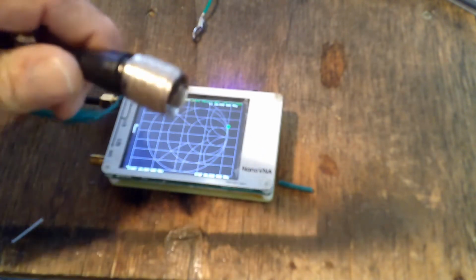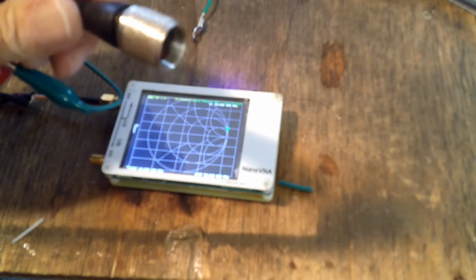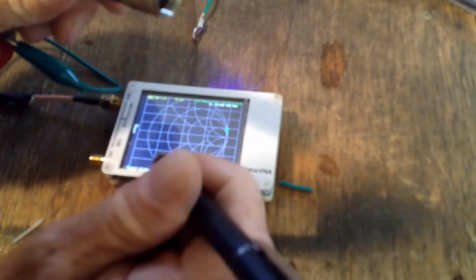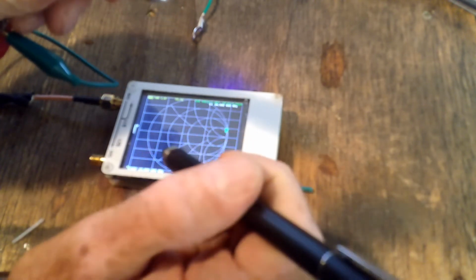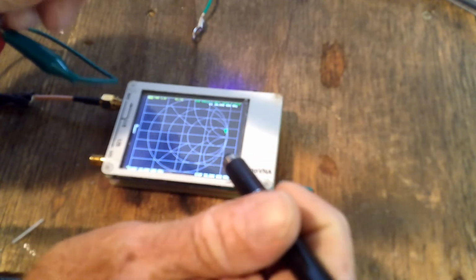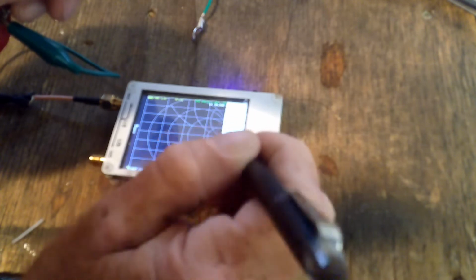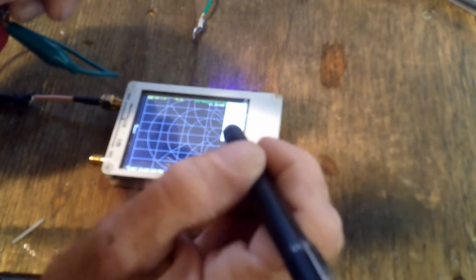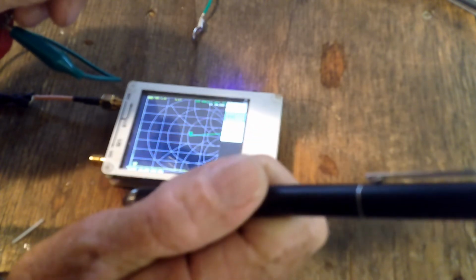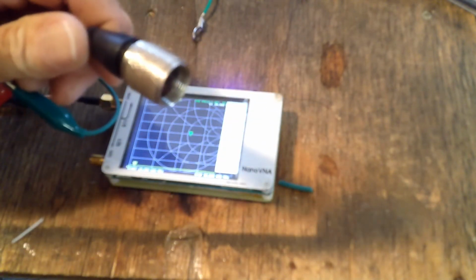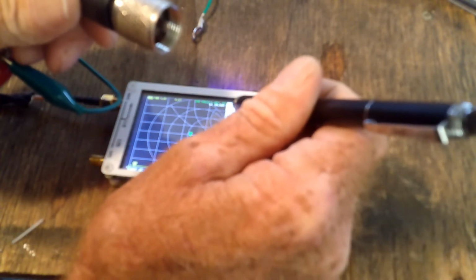And of course it's showing everything all opened up. I have this cable connected here. You can see that. And so what I'm going to do is try to calibrate everything with this and try to get things zeroed out. And here's how I do it. I've got my start and stop frequencies set to 20 megahertz start, 30 megahertz stop. And so we'll go through our calibration. Go to cal. I'm going to reset everything. And then I'm going to go to calibrate. And I'm just going to leave this open, just like this. And I'm going to call that the open calibration.